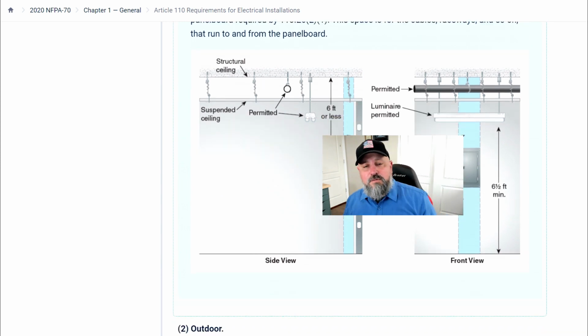And basically that's just what I want to go over. We'll go over outdoor on another video, but I hope that it cleared up some confusion, and hopefully you understand this. And if any of the other trades try to go in that space, then you just tell them, that's not up to code. You can't have it there. Talk to your PM, talk to the GC. Nothing is allowed in that space, 6 feet above our panel boards, gear or anything. And then make sure you have the right working space, that you're measuring from the front of the cabinets and making those correct conditions, 1, 2, or 3.